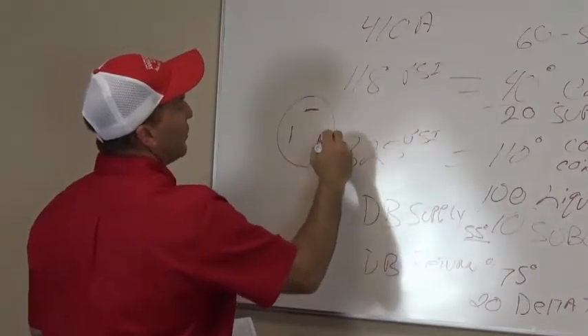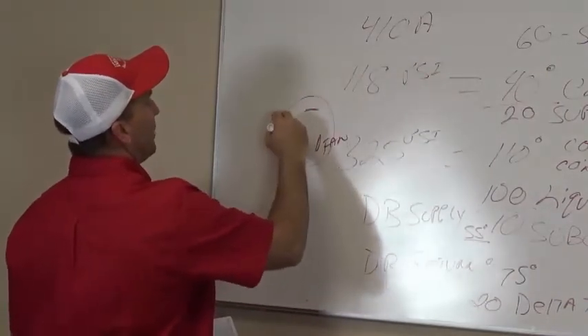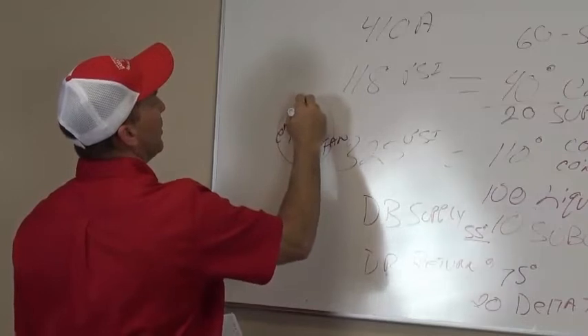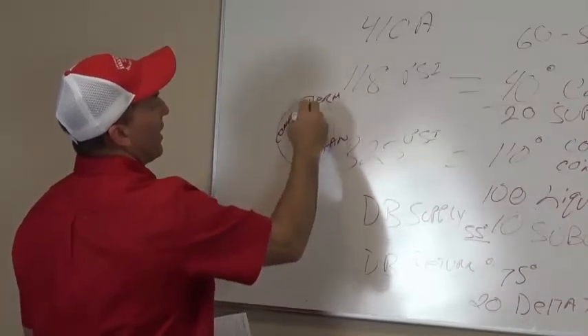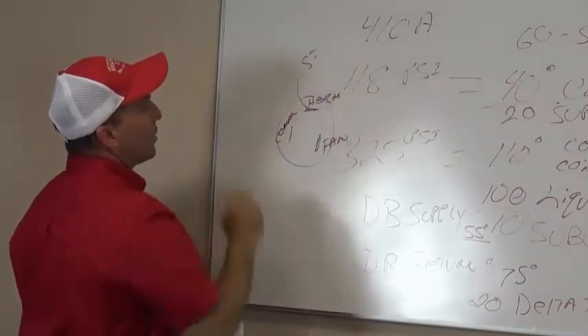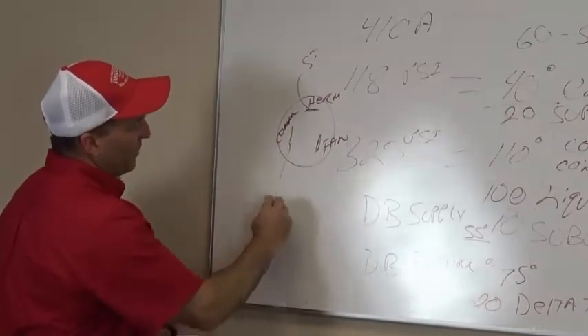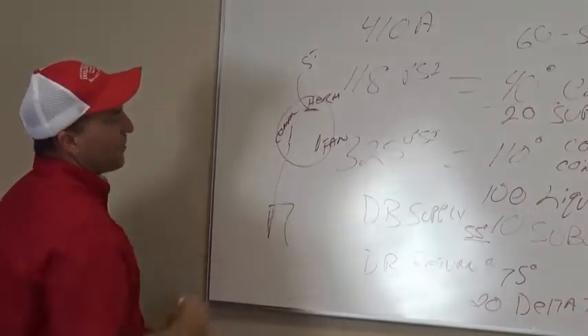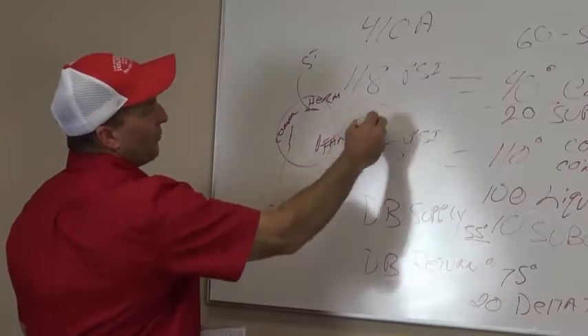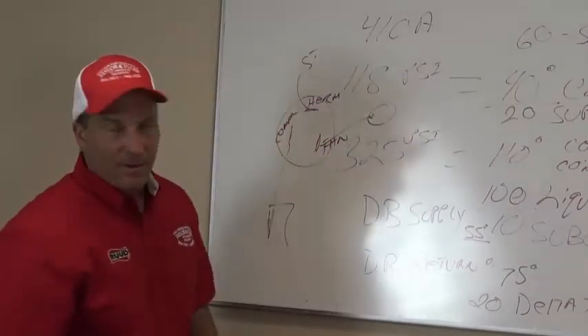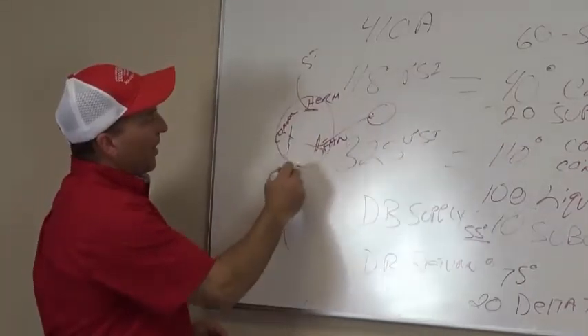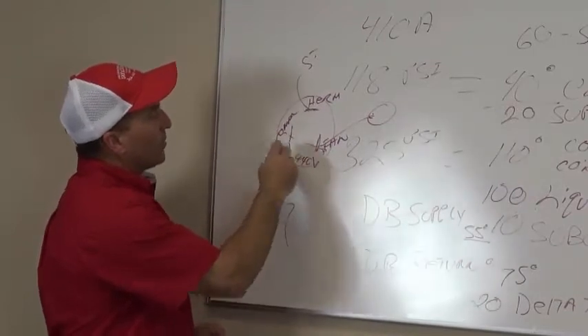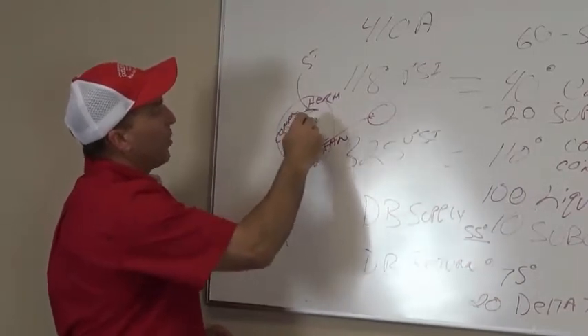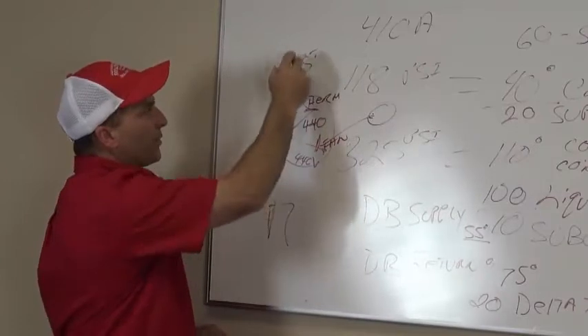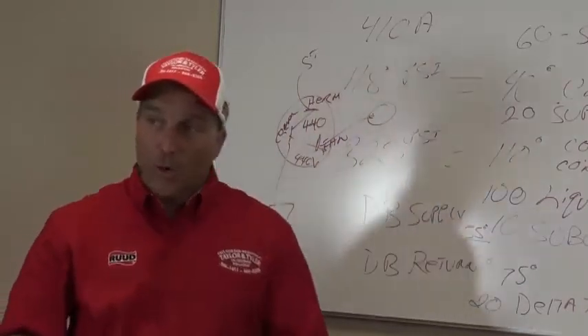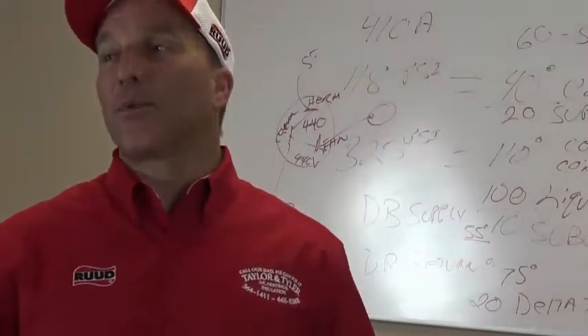This one over here is your fan. This one here is your common. And this one here is hermetic. Hermetic is going to the start winding on your compressor. Common is going over here to your contactor. Okay? And your fan is going to your fan motor over here for the capacitor. Between common and fan, there's 440 volts. Between common and hermetic, there's 440 volts, which brings 440 volts to your start winding to start that compressor.